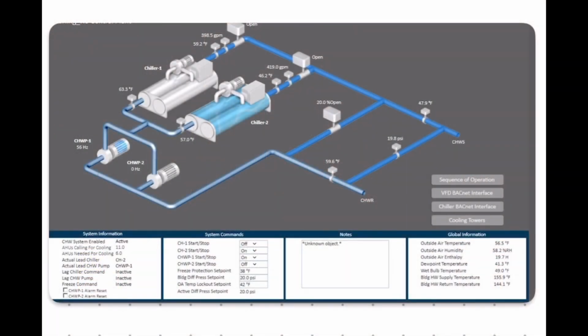So now we're looking at the chillers, and we're gonna talk about the cooling side of the chillers. In this case, you have chiller number 1 and chiller number 2. You also have chill water pump 1, chill water pump 2, and I'm gonna explain the water cycle and how it runs. In this case, only chiller 2 and pump 1 are the ones that are running. So let's go through it. This is the same building that we've been looking at for the VAV boxes and all of that.